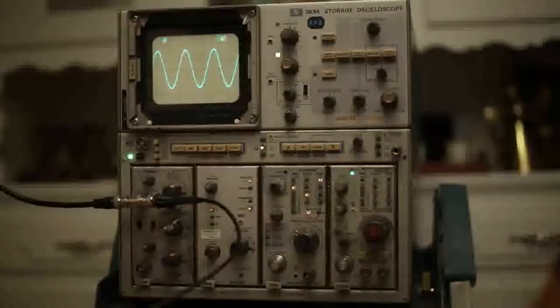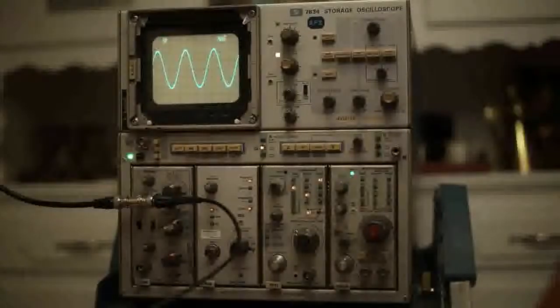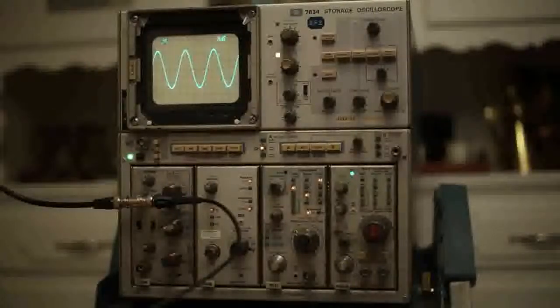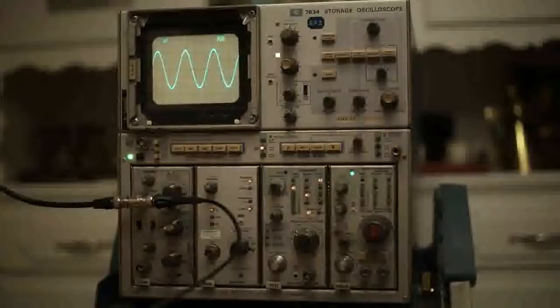This particular oscilloscope has two amplifier modules. One is a dual channel 200 megahertz bandwidth module, the other is a single channel 250 megahertz bandwidth module. This oscilloscope also has two time base modules, both of which have slightly different features.